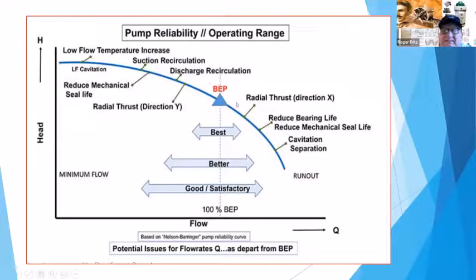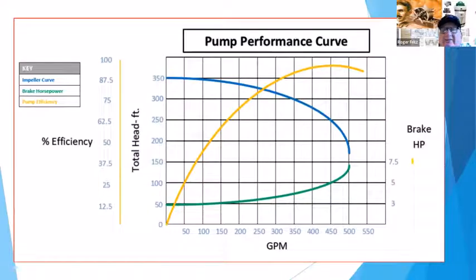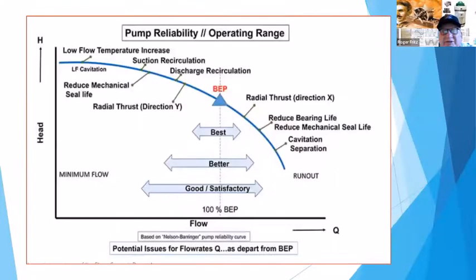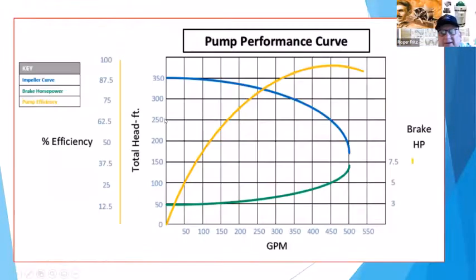I've seen differentials in just getting people running at the proper part of the pump curve save as much as 30% of the power, and then control it properly from there. And you didn't even need a VFD. Especially in irrigation, you have to be careful because you're looking at total GPM. You want to get a certain amount of acre feet of water to the customer, to the job site. But again, they've got complex systems with all kinds of output filters. So they overcome a lot of that with less effective engineering of the pump curves to the application. They overcome it by tweaking it with a VFD, which works, but you're maybe still creating losses and not operating at the proper head feet.